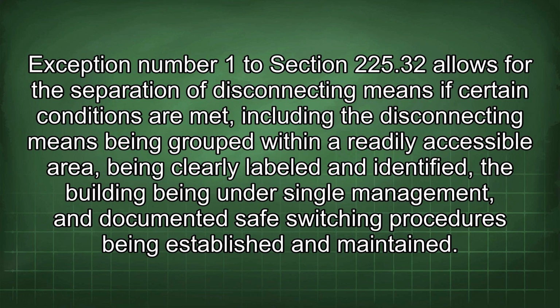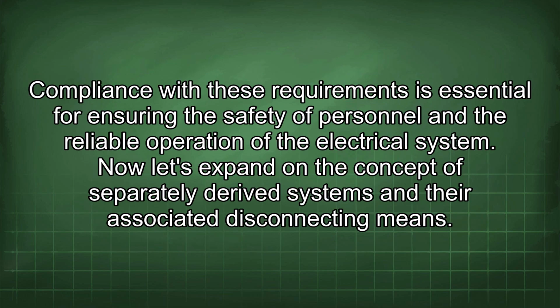225.32 allows for the separation of disconnecting means if certain conditions are met, including the disconnecting means being grouped within a readily accessible area, being clearly labeled and identified, the building being under single management, and documented safe switching procedures being established and maintained. Compliance with these requirements is essential for ensuring the safety of personnel and the reliable operation of the electrical system. Now let's expand on the concept of separately derived systems and their associated disconnecting means.